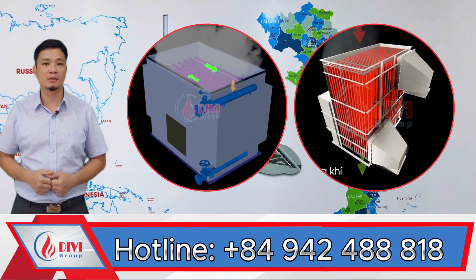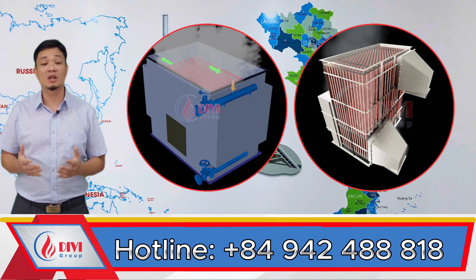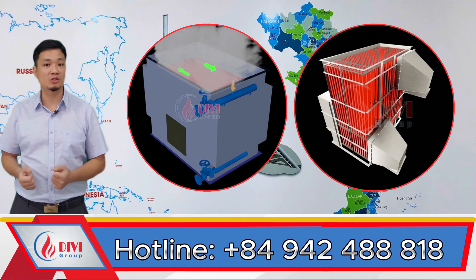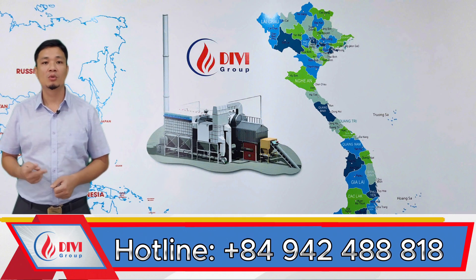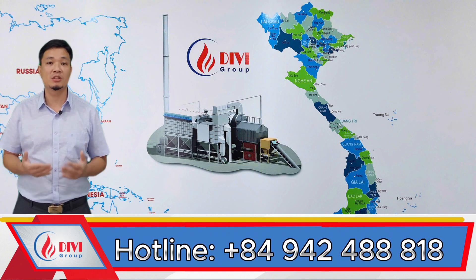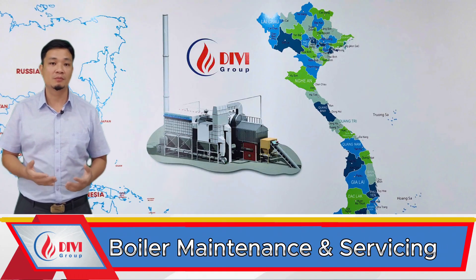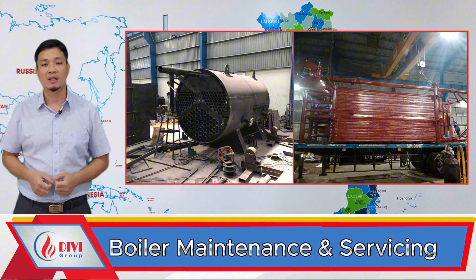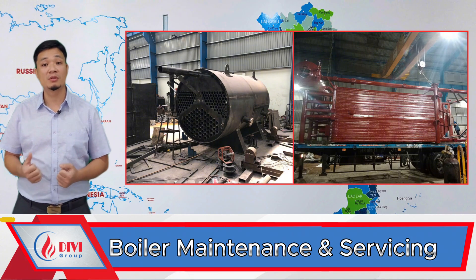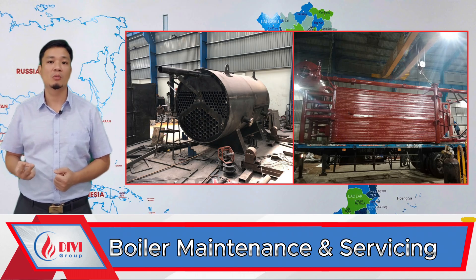But here's the key point: this slight difference in heat transfer efficiency can be compensated for by using heat recovery components downstream, like economizers and air preheaters. So in the end, when both designs are properly engineered, the total thermal efficiency of the two boiler types is virtually the same. Now let me go a bit deeper into the topic of boiler maintenance. Since all of the auxiliary equipment aside from the convective heat transfer section is practically identical in both boiler types, the general maintenance tasks are essentially the same. So today we'll just focus on comparing the convective sections of the two boiler designs.